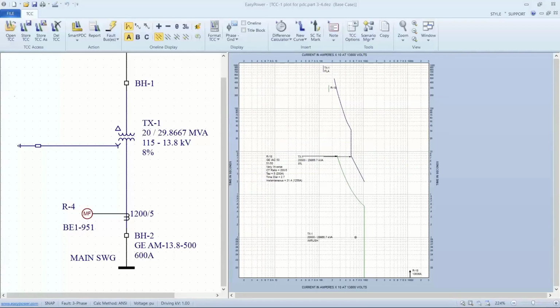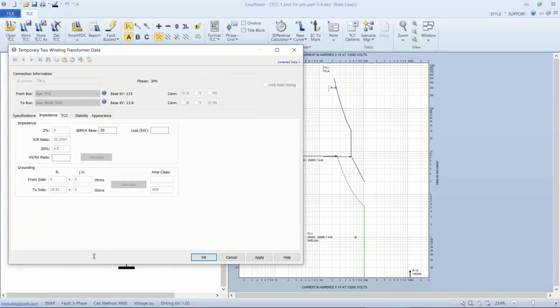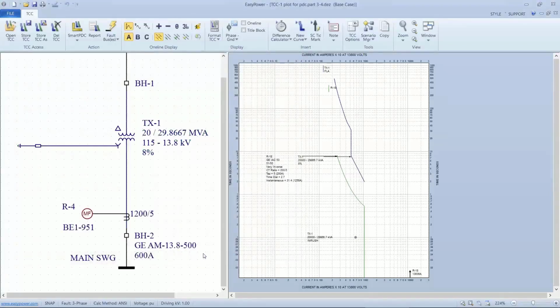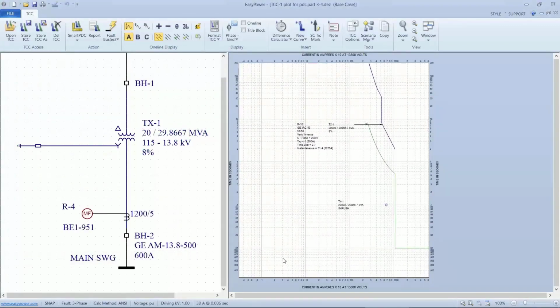So the reason there's only one curve is because this is not a hard grounded transformer. This has got a high resistance ground connection, and it's set up when we do the impedance setting for this transformer. So let's go back and talk about that. What it amounts to, if I look at the transformer dialog box and at the impedance curve, we've got a 400 amp resistor set up in the neutral leg. So that means the maximum current that the system will see is 400 amps through that ground connection. Well, 400 amps is going to be somewhere down here in the mud, and so it's never going to be in this approximation of the phase current, which can be in tens of thousands of amps.